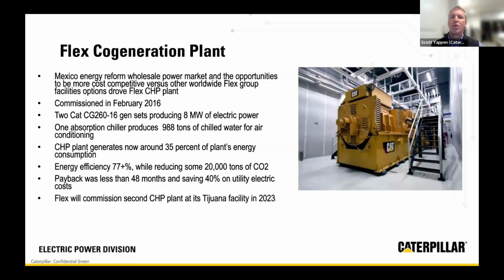It's got two Caterpillar natural gas fueled generator sets with a nameplate of 4 megawatts each, so 8 megawatts total nameplate. But after subtracting parasitic electrical loads like radiator coolers and other electrical equipment, we're looking at around 3.75 megawatts each, or around 7.5 megawatts total for the two engine generators.